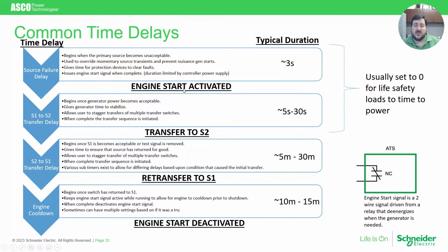When the generator is started, we wait for it to come up to proper voltage. And once it comes up to proper voltage, we wait an additional delay, which again can be user configured in duration, or completely eliminated, but commonly is set to a short duration to allow the generator a little bit of additional time to stabilize its voltage. Also, if you have multiple switches in the equipment, you can set different transfer switches to different time delays. So ATS 1 transfers at 5 seconds, number 2 at 10 seconds, number 3 at 15 seconds, so that they do not all transfer at once and block load the generator, causing potential issues.